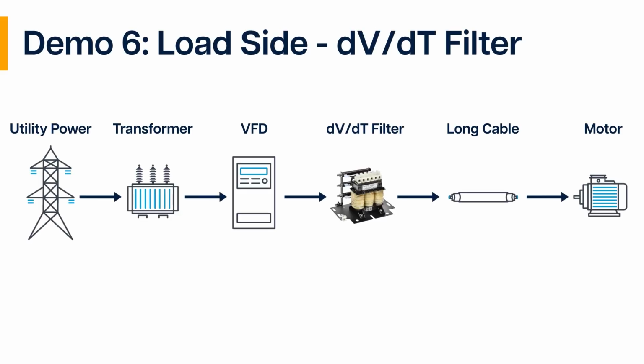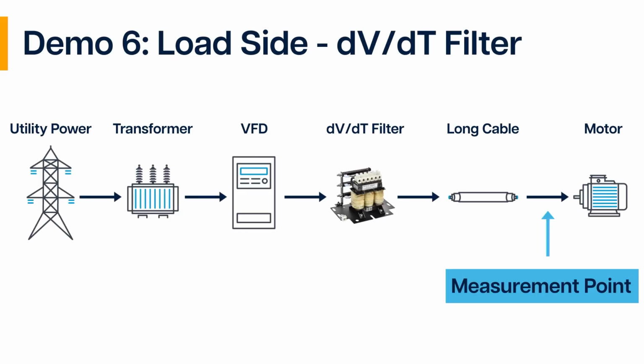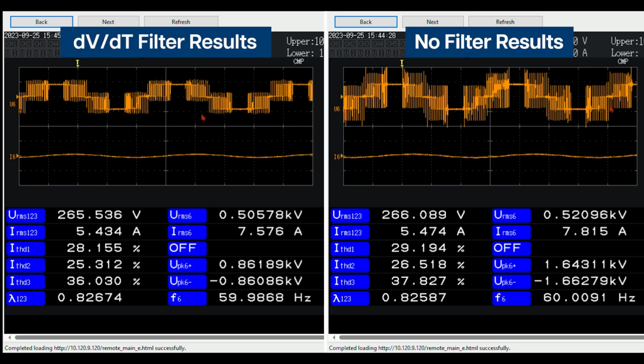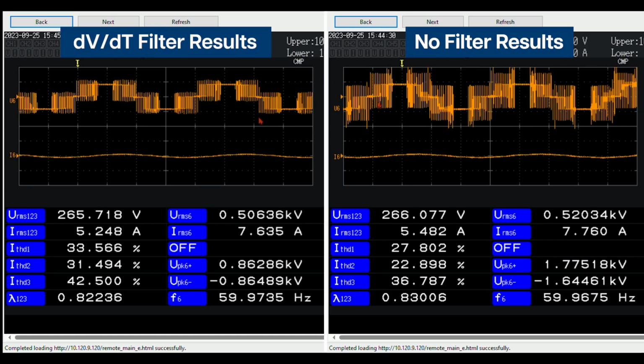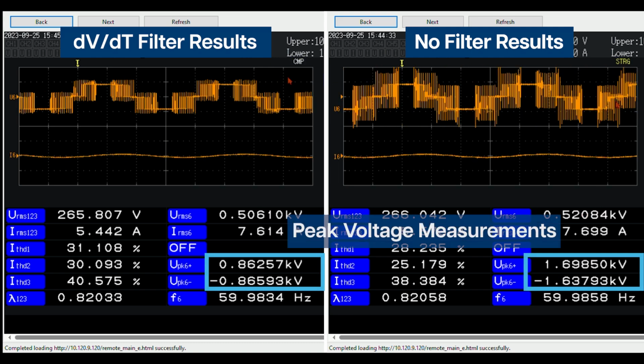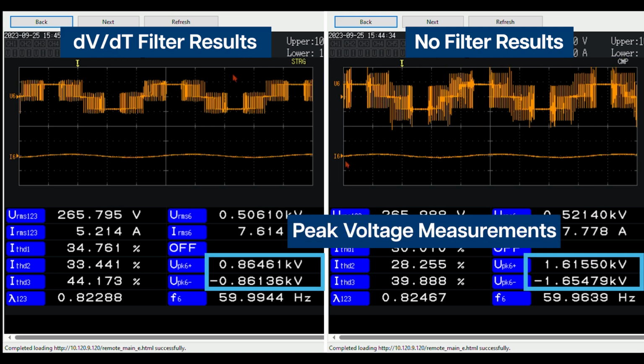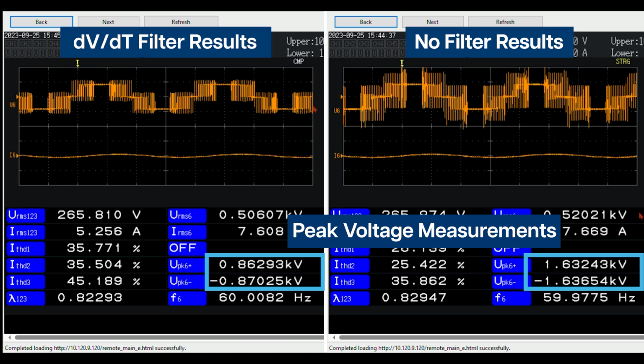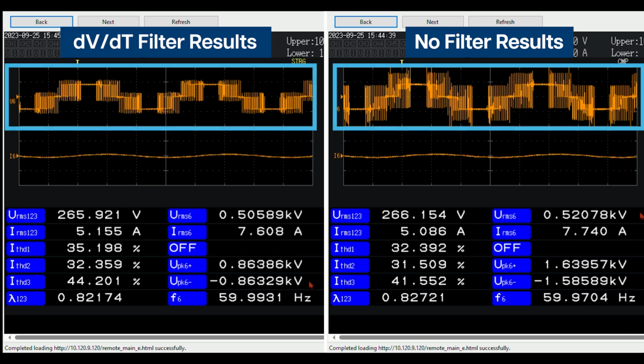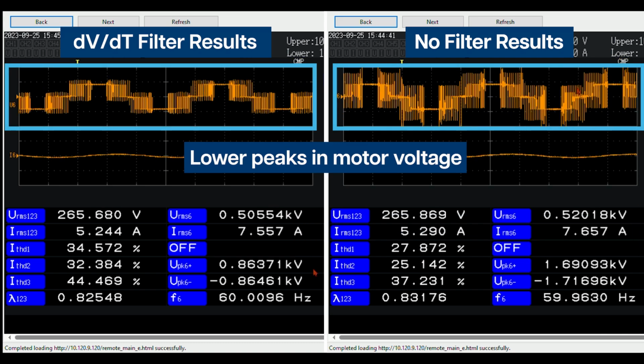In Demo 6, we'll integrate a dV/dT filter into the circuit. Positioned at the drive's output and suitable for cable lengths up to 1000 feet, the dV/dT filter aims to reduce voltage peaks to below 1000 volts, and it will decrease the rate of voltage changes.